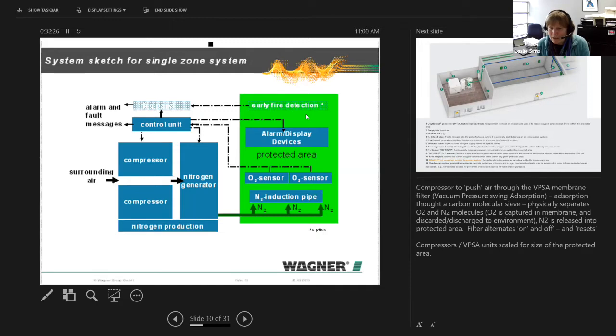I don't want to go into too much more detail about the generation of the nitrogen. You're seeing this on the protection on dry pipe systems these days, where we're putting nitrogen within the system to reduce corrosion. Very similar idea. You get a nitrogen generator and it's always managing and pushing a little bit of nitrogen into the dry pipe system, and you're monitoring that environment.